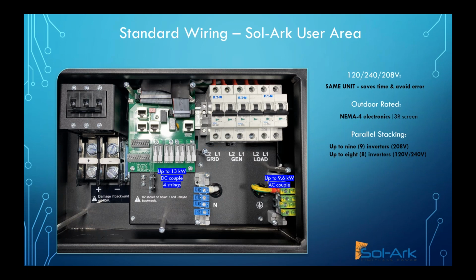You can AC couple. This is our 12K, so this is a Sol-Ark 12K statement. You can AC couple up to 9.6 kilowatts of solar directly from an existing system and directly from an existing solar inverter. You can bring up to 13 kilowatts of DC PV directly into the Sol-Ark. And again, we have 2 MPPT controllers with 2 strings each. So right above where it says 13 kilowatts, those 8 white toggle switches are the solar PV inputs. In the upper left corner, above the battery terminals, you can see a 250 amp battery breaker that's built in. And in the opposite corner, for the grid, the generator, and the load, we have 63, 50, and 63 amp breakers built in respectively.